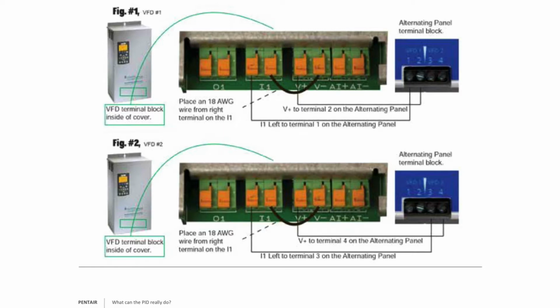So for example, how these are often used is a dairy operation, for example, has 2 5-horsepower pumps, and they want to equally wear them. So on day one sees the charge and it's going to run lag because there's voltage going down to the input, and that voltage tells it to look at the secondary input of pressure setting. So it runs at, say, 55. And it will maintain 55 psi when needed, but it will not turn on until the pressure point drops to 50. Now, if you look at the second drive number 2, it doesn't see the voltage, so there's no voltage on the input to influence it, so it's going to run at the full 60 psi, turning on at 55.